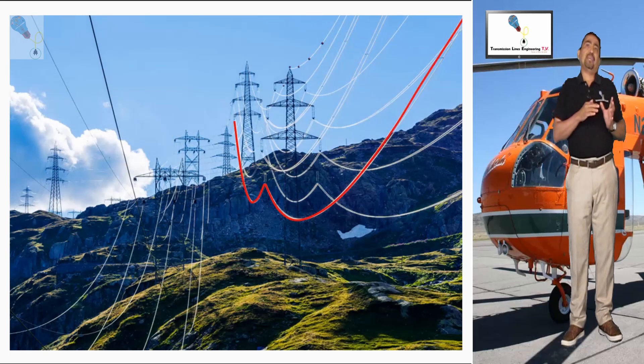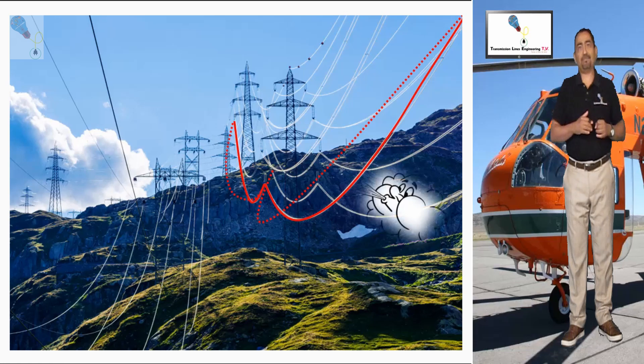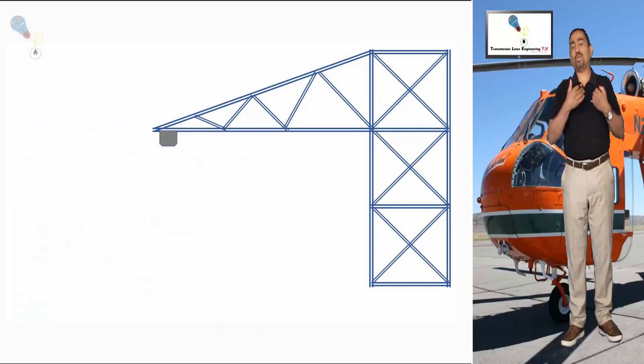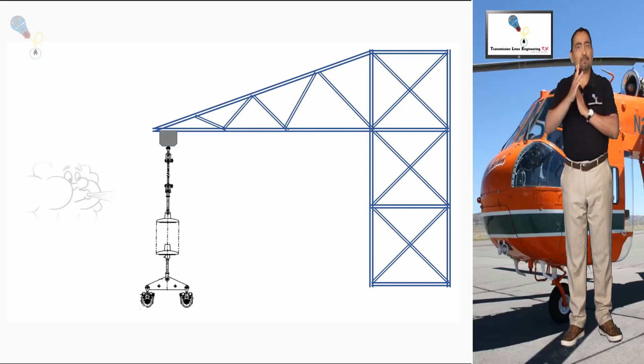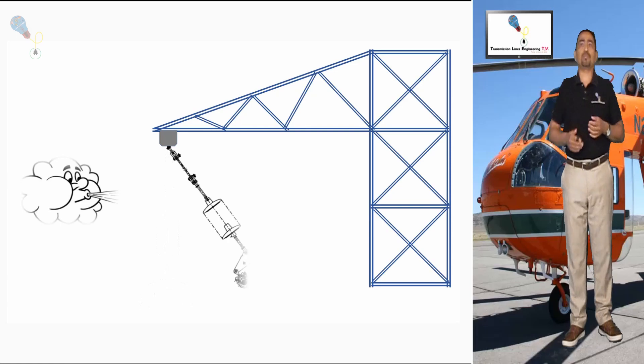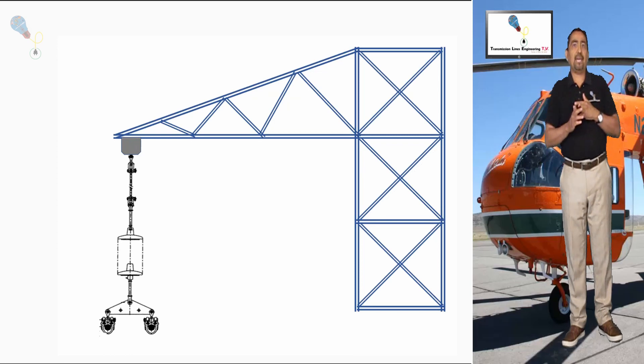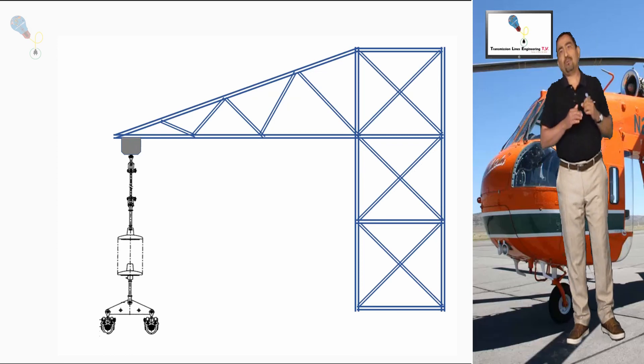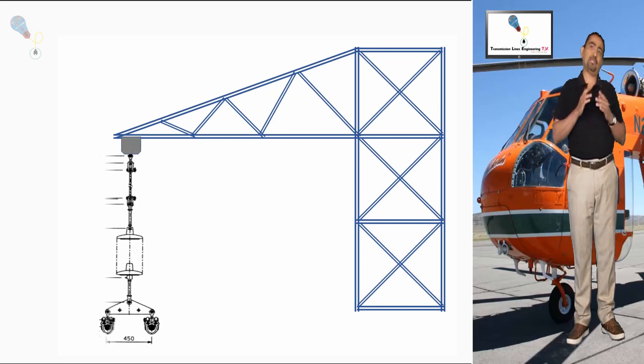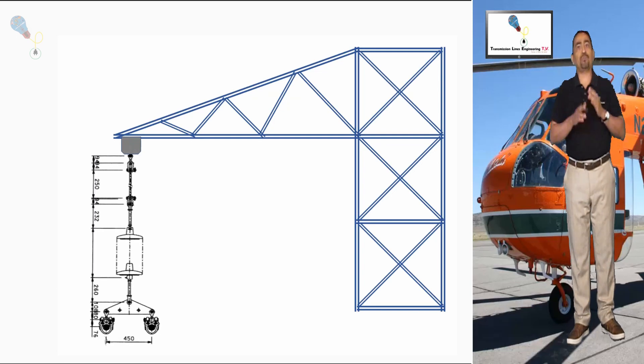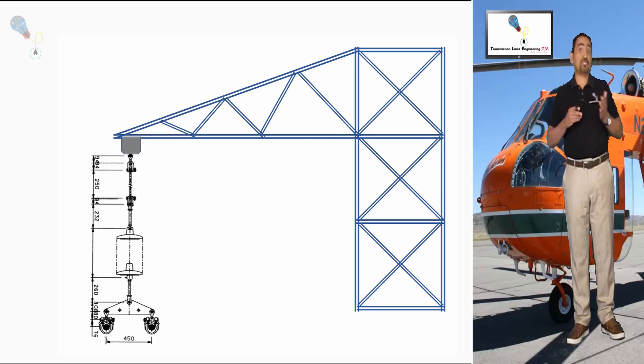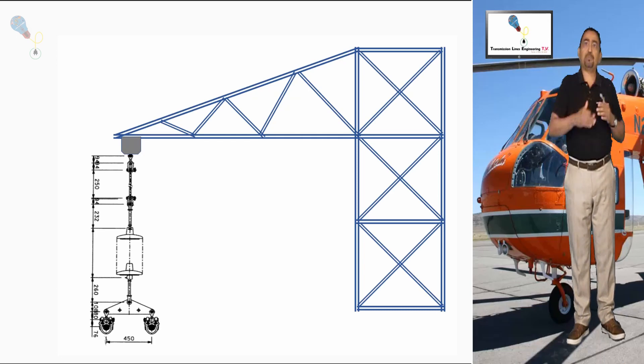The swinging effect is present on all types of cables. But in addition to the swing on cables, it is necessary to consider the swinging of the hardware assemblies. In the case of vertical suspension assemblies, it is directly affected by the wind and subject to swing. So it will be necessary to have a complete assembly drawing indicating the dimensions of each component, from the first shackle connected to the attachment point on the structure to the conductor clamp.